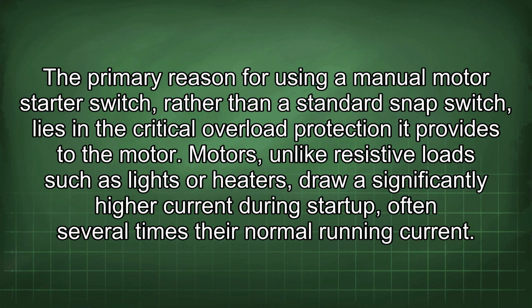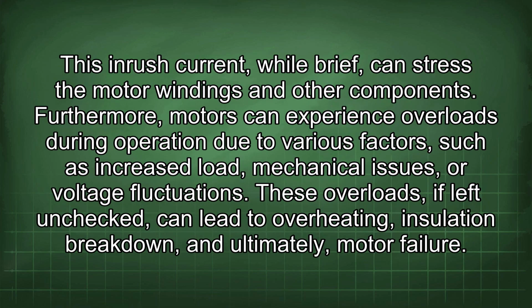Motors, unlike resistive loads such as lights or heaters, draw a significantly higher current during startup, often several times their normal running current. This inrush current, while brief, can stress the motor windings and other components. Furthermore, motors can experience overloads during operation due to various factors such as increased load, mechanical issues, or voltage fluctuations. These overloads, if left unchecked, can lead to overheating, insulation breakdown, and ultimately, motor failure.